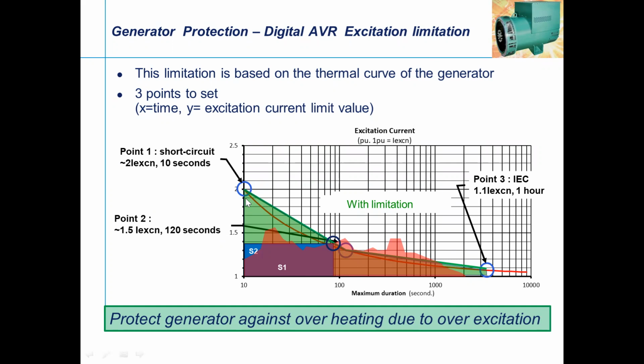And again, for the excitation, how much is the tripping time, what time period it should be, this can also be set in the excitation limit. The excitation will remove the power to the exciter, so the voltage collapses and the generator will be out of the system. So it protects the generator from over excitation, even though the demand has come to that. Of course, failures can happen with non-proper settings. This is where experts like the manufacturer come into play. A good commissioning engineer comes into play.